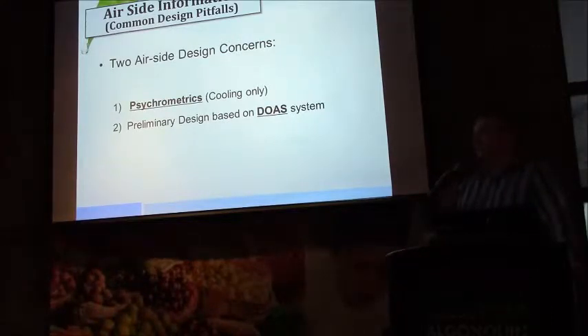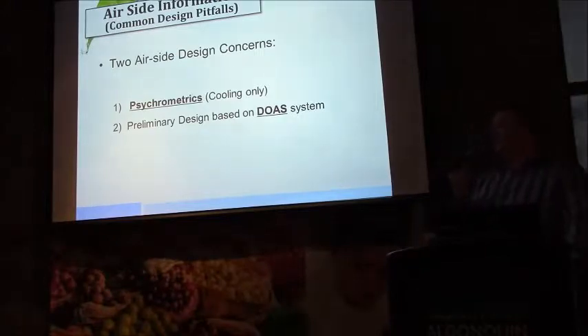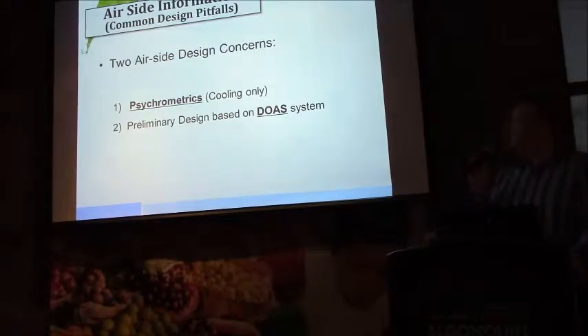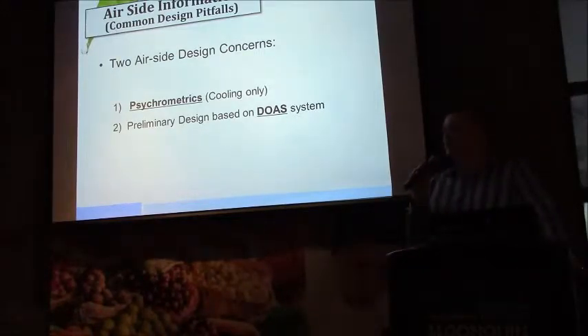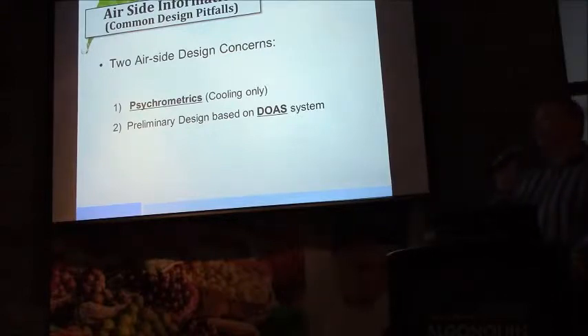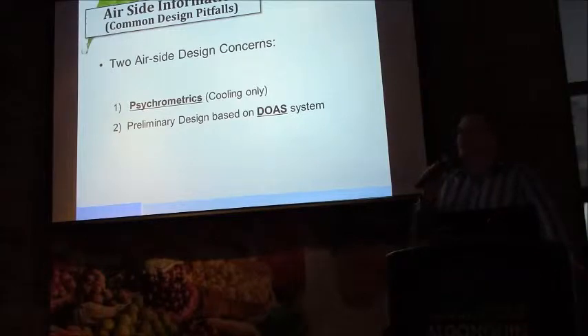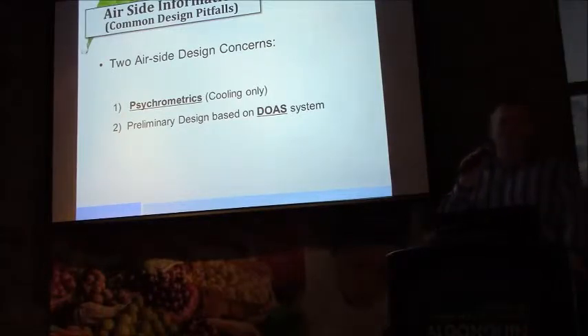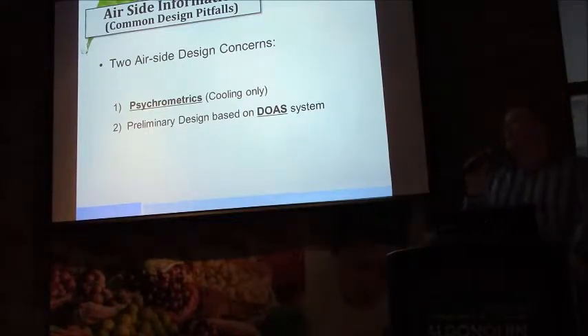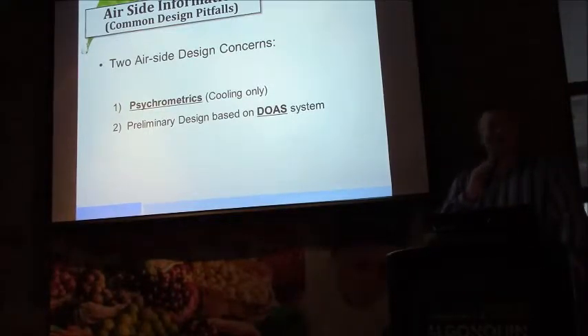which seems like a lot, but it's frankly not when we compare it against a rough rule of thumb on a conventional, say, all air system, and this isn't a slight against all air systems. If we were to consider that at 400 CFM per ton, even a slight increase in the primary air to offset the latent loads, with good beam design, we could conceivably see in the neighborhood of 200 to even 300 CFM per ton at the most. And beyond that, maybe an active beam for that particular space may not be a good solution.